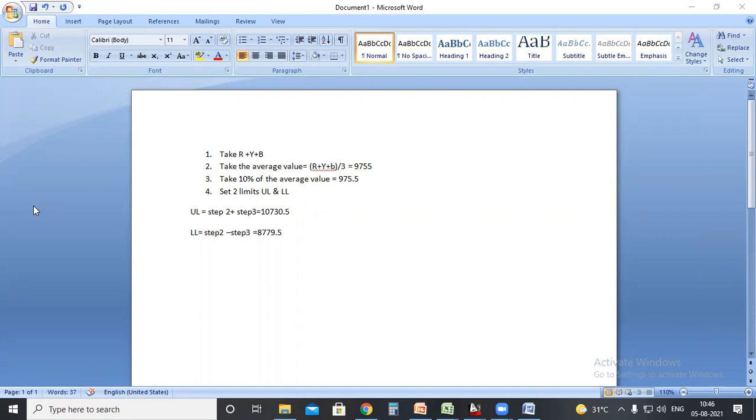So in this example, you could balance by shifting the complete circuits from BR2 to Y phase and guest room to R phase. But in some cases, that would not be possible, so don't stick to that. You can just move the circuits also. But make sure that two circuits are not coming together in a single switchboard, because in future, if someone is coming for maintenance, there is a possibility to rewire the circuit separately. If it is two equal loads, not an issue, but I'm telling you just to make sure that you can separate them in two switchboards.